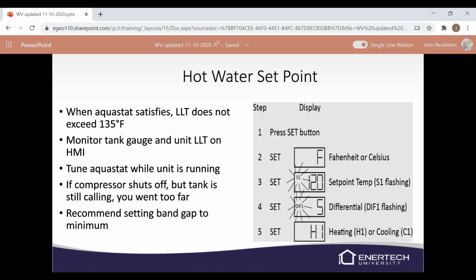I don't really care what the aquastat is set at. We just don't want that leaving load temperature above 135. Aquastats can be off by quite a few degrees straight out of the box. So just make sure we're not getting too hot of water.